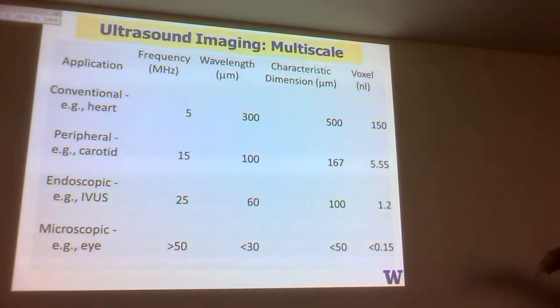Because your axial resolution is at worst a wavelength, can be a little bit less, or quite a bit less than the wavelength, but typically if you want to pick a number, it's the wavelength. So if you're at 5 megahertz, you have 300 micron axial resolution. Characteristic dimension means sort of the diameter of a voxel size, and that's about 500 micron.